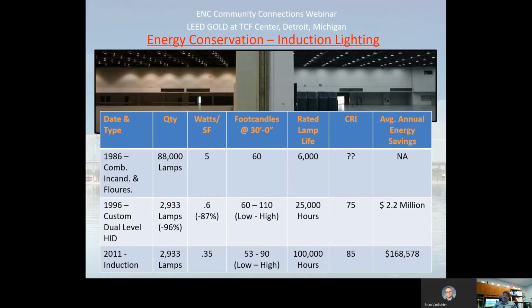In '96, we embarked on an energy conservation measure where we replaced those 88,000 lamps with 2,933 HID dual level specially made fixtures for us, and it did tremendous things. We went from 5 watts per square foot down to 0.6 watts per square foot. Our lighting levels went up from 60 to 110 easily, and the life of our fixtures went from always having to change them to maybe having to change bulbs every 3 years. CRI went to 75, and what that means, if you look at the graphic there, on the left-hand side is before, and on the right-hand side is the after for induction lights. So let's go with the before, the exhibit halls with the HIDs. I don't have a picture of the 88,000 fixtures, but the big one in this story is the $2.2 million a year in energy savings that we were doing over switching out to these HIDs.